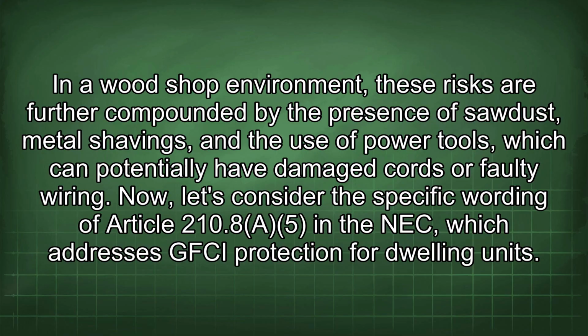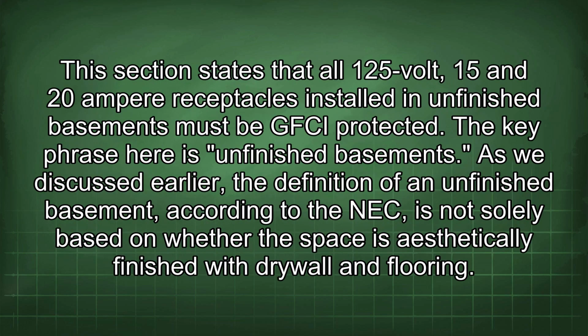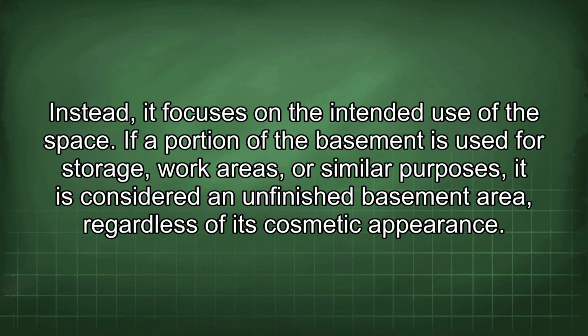Now, let's consider the specific wording of Article 210.8(A)(5) in the NEC, which addresses GFCI protection for dwelling units. This section states that all 125-volt, 15 and 20 ampere receptacles installed in unfinished basements must be GFCI protected. The key phrase here is unfinished basements. As we discussed earlier, the definition of an unfinished basement according to the NEC is not solely based on whether the space is aesthetically finished with drywall and flooring. Instead, it focuses on the intended use of the space.